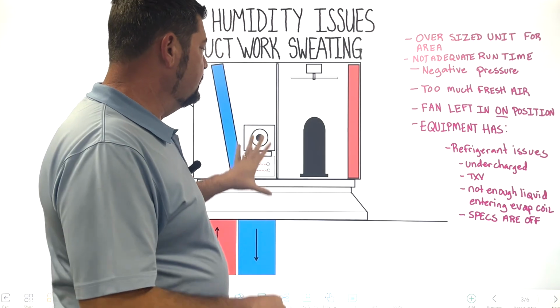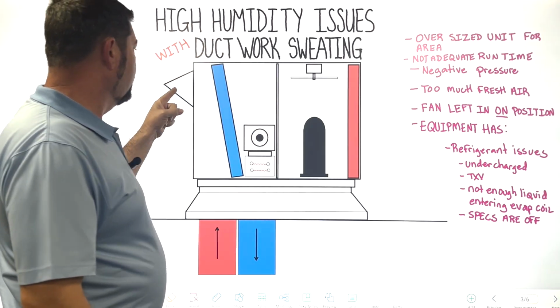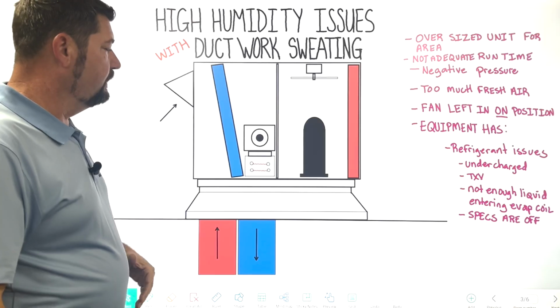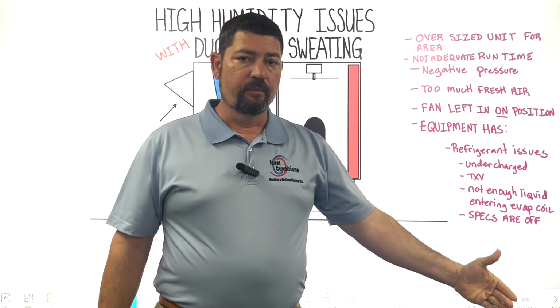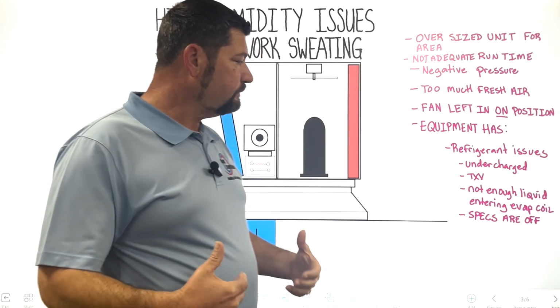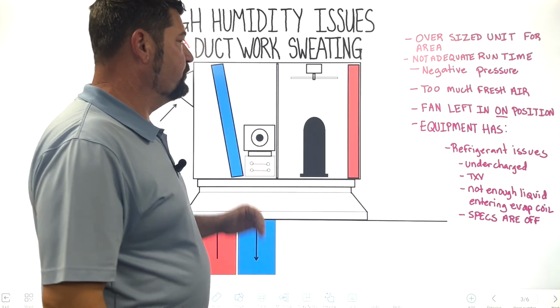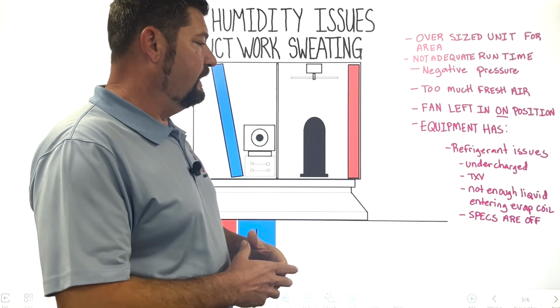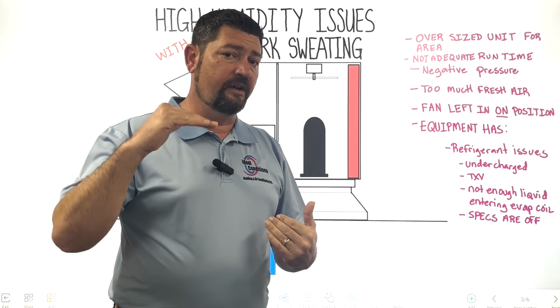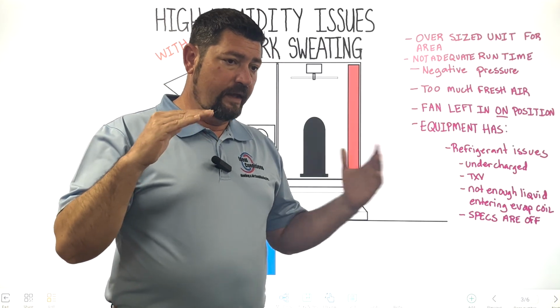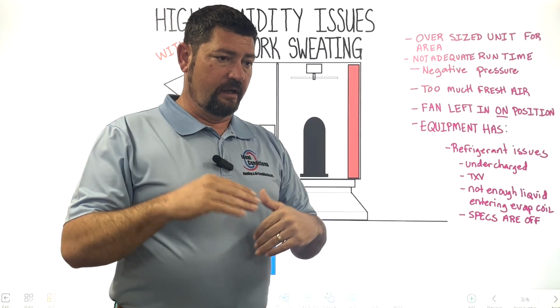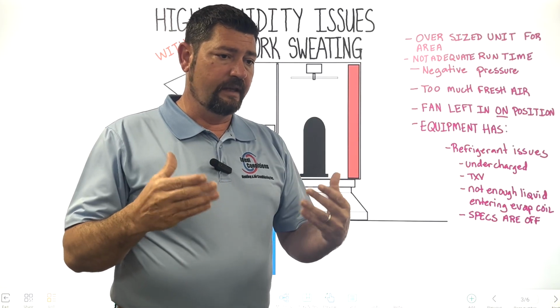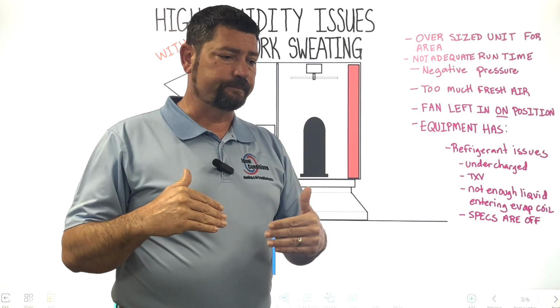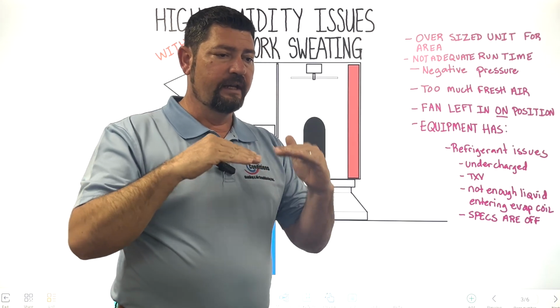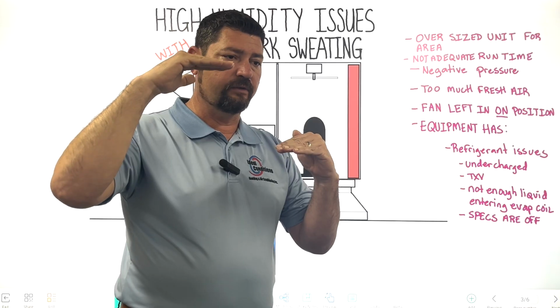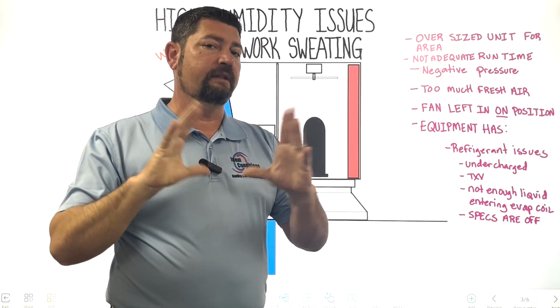Typically, what we see in addition with that is if these fresh air dampers are not installed, then naturally there will be a negative pressure on the building, and there's nothing there to mitigate that negative pressure by adding additional outside air in. And then that high humidity that is left as a result of a short cycle, with no outside air adding to the structure to balloon it, then what will happen is you will reach a dew point. You'll drop the temperature so low that because the humidity is still at a higher level, that humidity is just going to start collecting on anything that's cold.